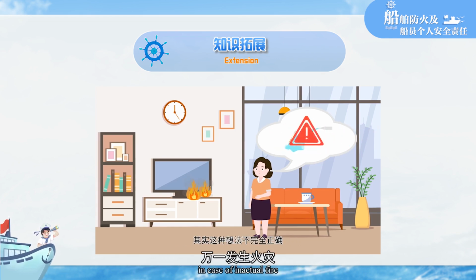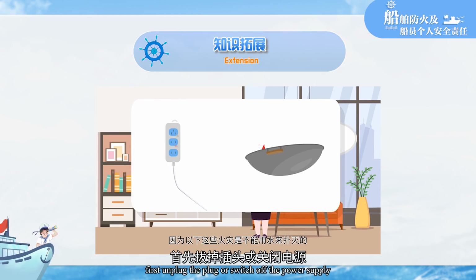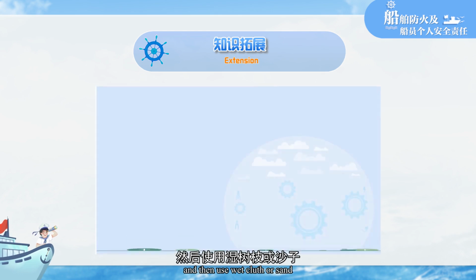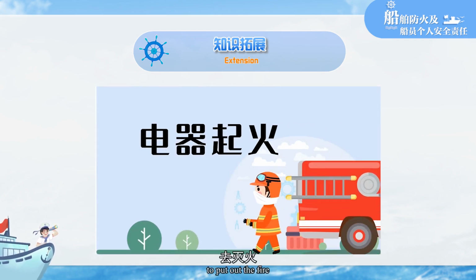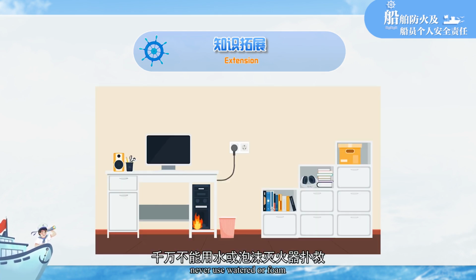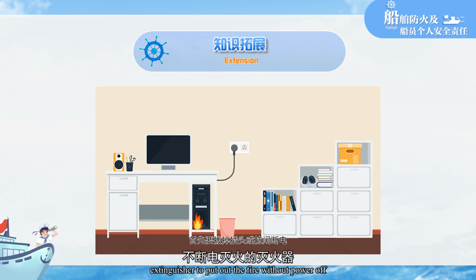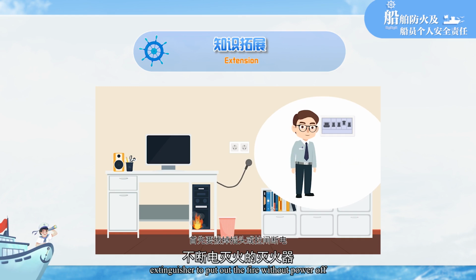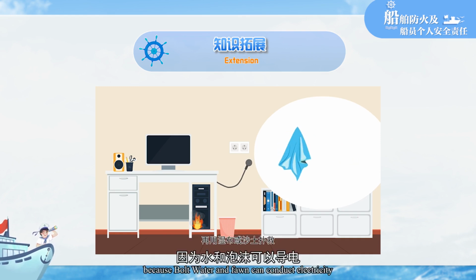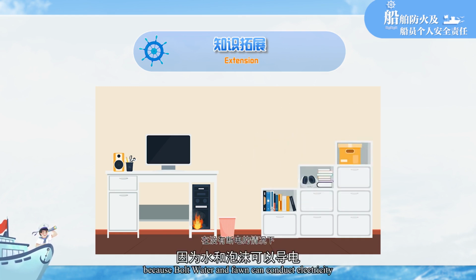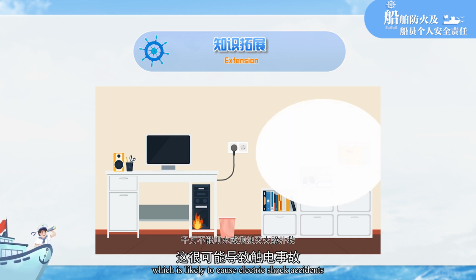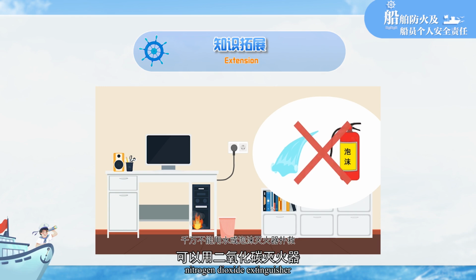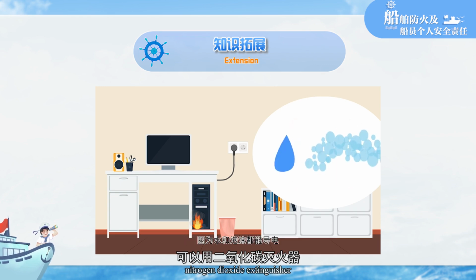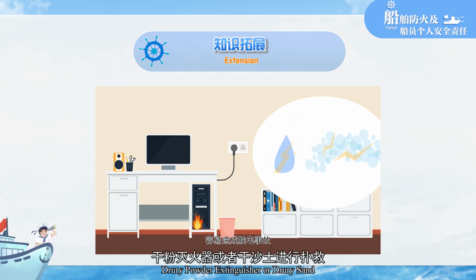In case of electrical fire, first unplug the plug or switch off the power supply and then use a wet cloth or sand to put out the fire. Never use water or a foam extinguisher to put out the fire without power off, because both water and foam can conduct electricity, which is likely to cause electric shock accidents. A carbon dioxide extinguisher, dry powder extinguisher, or dry sand can be used to put out the fire.